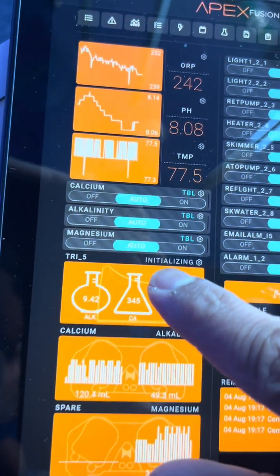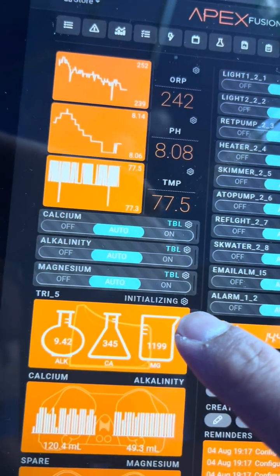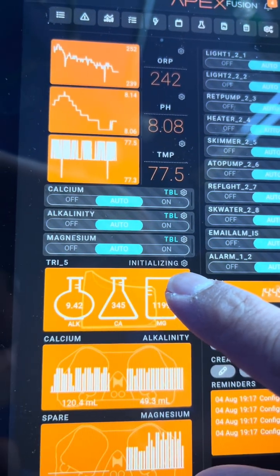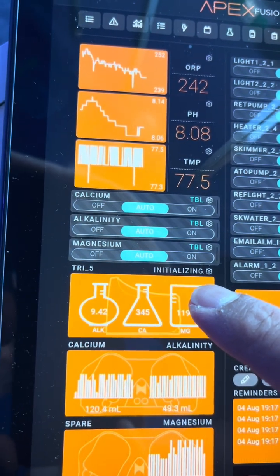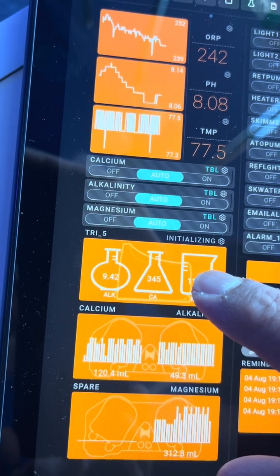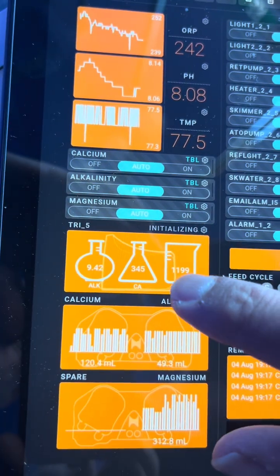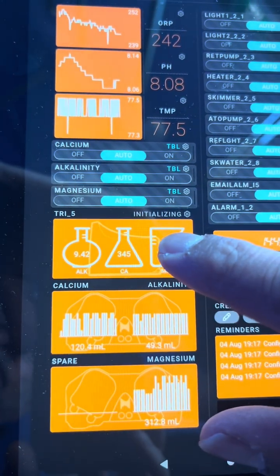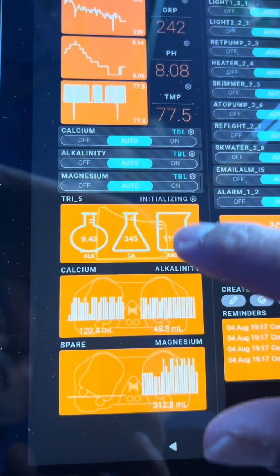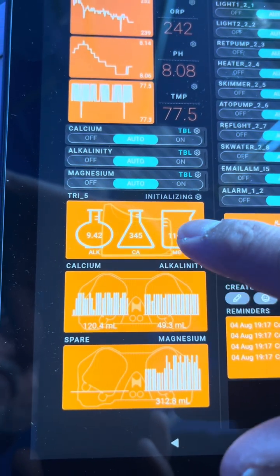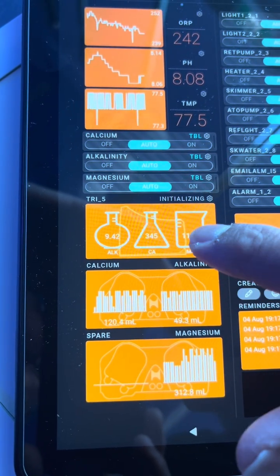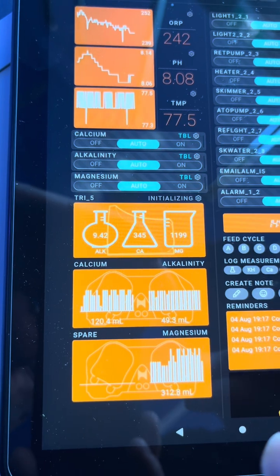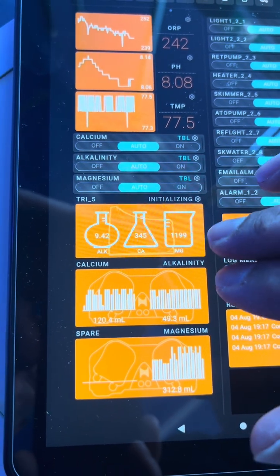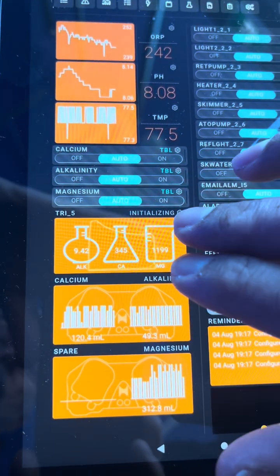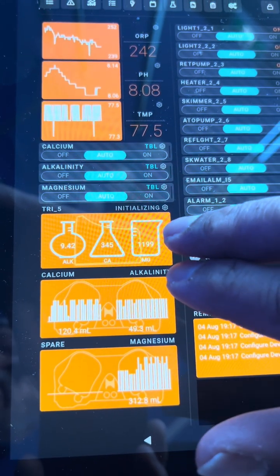We're back on the screen here, and as you can see, it has already started initializing. So what it's going to be doing first is priming the intake line, basically drawing the calibration solution from the bottle that we have there. And it's going to prime that line and start the calibration process. Now, based on past calibrations that we've done on other customer setups for Trident, and what Neptune also mentions, an average calibration takes between 40 to 45 minutes. So you're going to leave this here, keep monitoring it in between, and then wait for the next steps once the calibration process is completed to see what the results are.